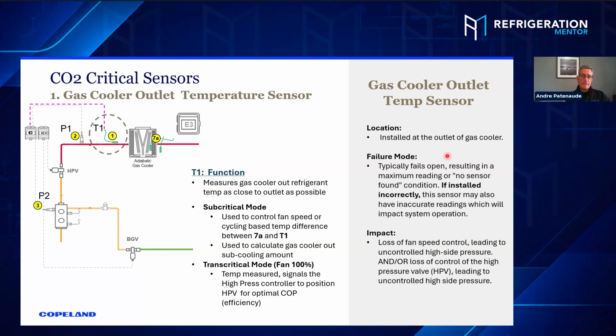So if that sensor T1 fails, it typically fails open, resulting in no sensor found. And you mentioned it earlier, Trevor. If it's not installed correctly, it's difficult for it to control. Sometimes it's just hanging. I've seen them just hanging in the ambient, not even measuring the gas cooler. I'm doing trainings now, and while I'm doing a training, I get the technicians to go out and take pictures of the sites, and of these critical sensors and what they look like, and they come back and I'm looking at some of them.